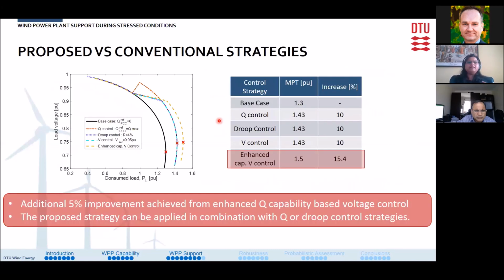When we compare the proposed strategy with the conventional strategies, we see that we get an increased maximum power transfer capability. An additional 5% improvement is achieved when compared to the conventional control strategies. And as I mentioned before, this can be applied in combination with Q or droop control. This strategy requires no installation of any additional resources.